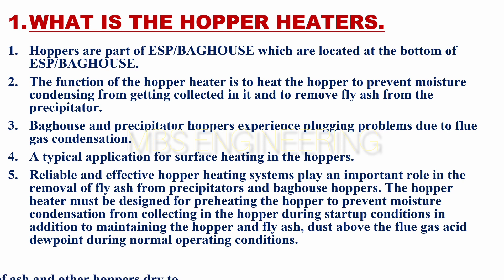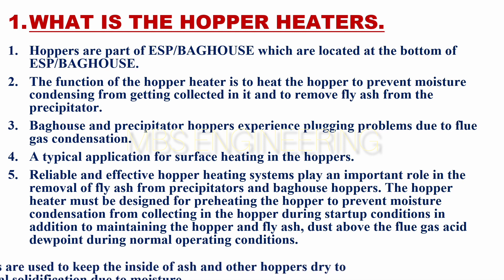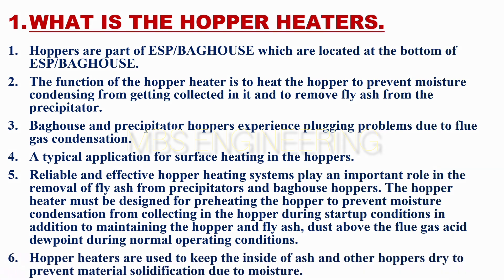The hopper heater must be designed for preheating the hopper to prevent moisture condensation from collecting in the hopper during startup conditions, in addition to maintaining the hopper and fly ash and dust above the flue gas acid dew point during normal operating conditions. Hopper heaters are used to keep the inside of ash and other hoppers dry to prevent material solidification due to moisture.